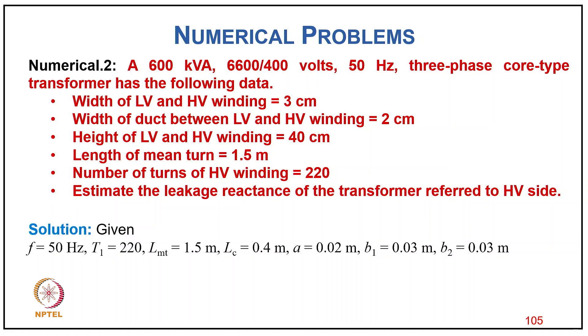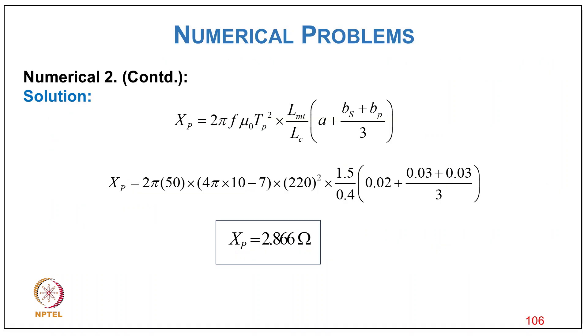Numerical problem 2: A 600 kVA, 6600/400 V, 50 Hz core-type transformer with: HV/LV winding widths 3 cm each, duct between LV and HV 2 cm, height of windings 40 cm, mean turn length 1.5 m, HV turns 220. Estimate leakage reactance referred to HV winding. From X1 = 2πf×μ₀×Tp²×LMT/Lc × [a + (bs+bp)/3], result is Xp = 2.866 Ω.